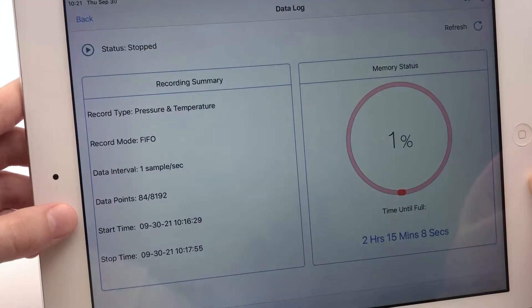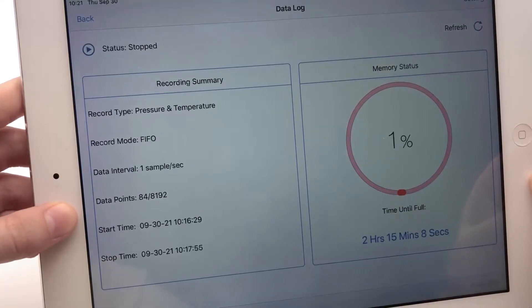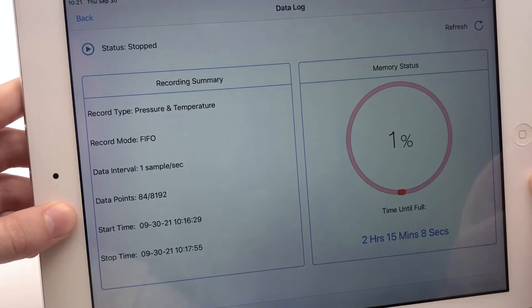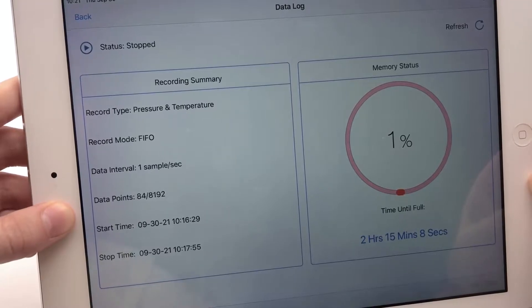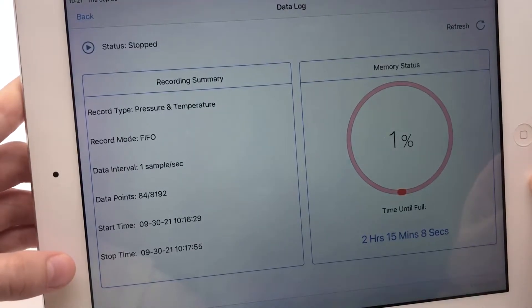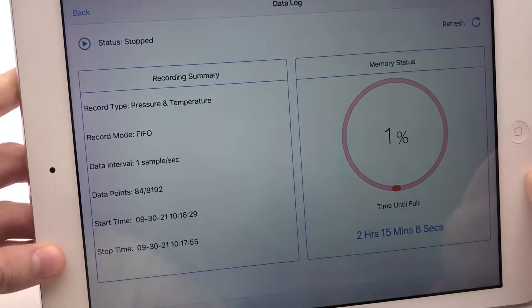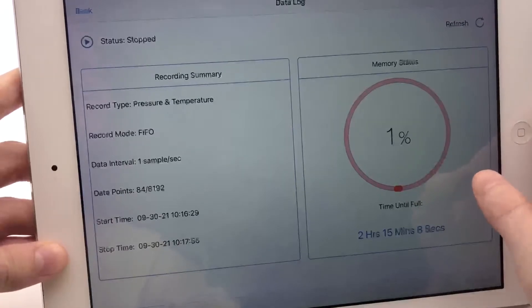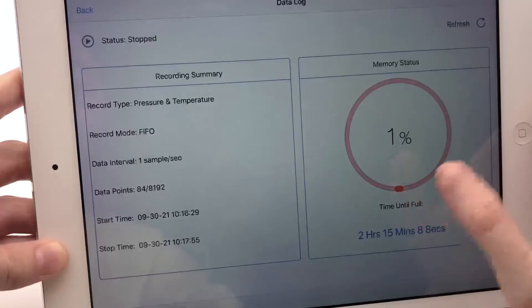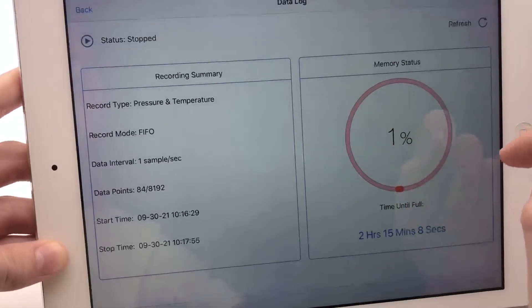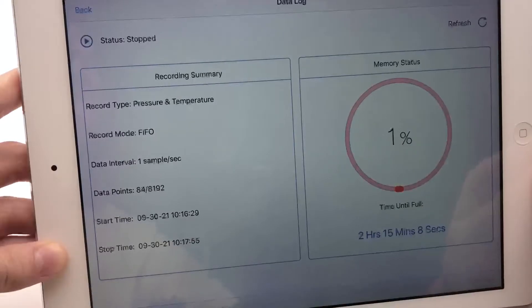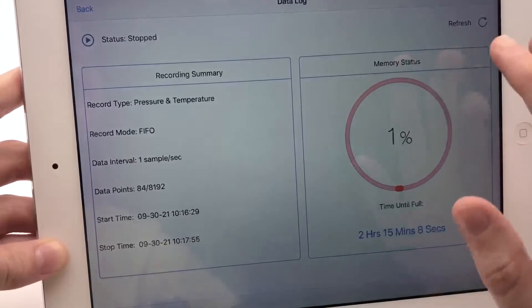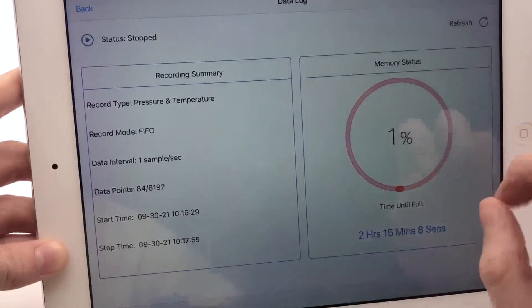The data point shows the number of readings that have already been taken and what the total limit for the logging session is. The start and stop time mark the start and stop timestamps of the data logging session. And over here, with memory status, it shows the percentage of memory used with a big analog indicator and the anticipated time until full. Time until full depends on the recording type and the data logging interval.